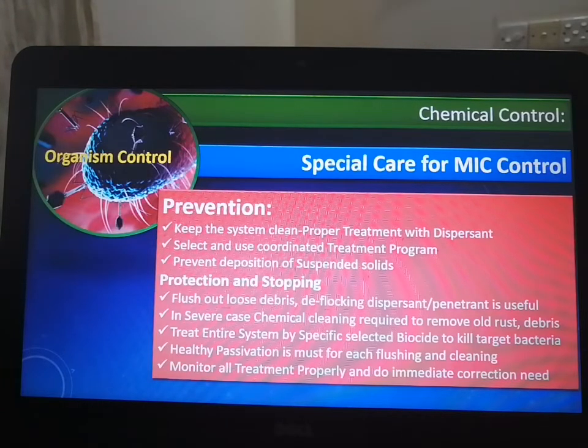That's why initial flushing and passivation is very important for every on-off of every plant, whether it's a boiler, a cooling tower, or any system. If we want to run again after a certain stop or shutdown, maybe a couple of months, days, or weeks, we definitely have to go for flushing and passivation. It's mandatory, otherwise we might have problems in the long run.